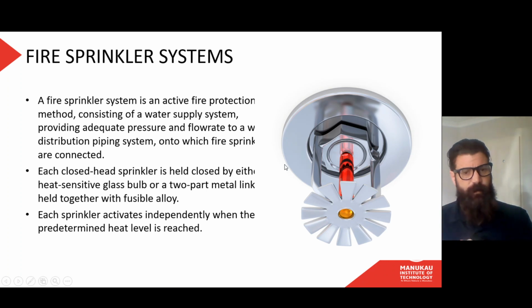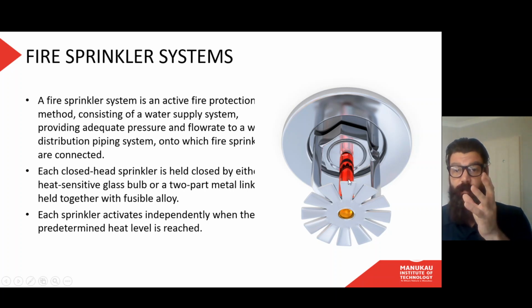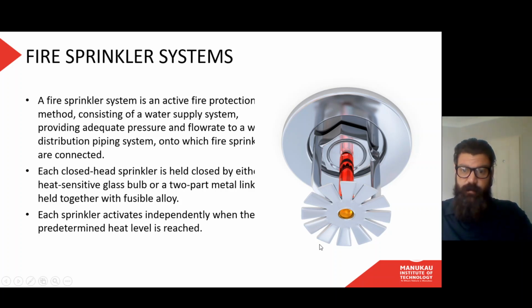Fire sprinkler system. As we talked about, we've got a really good picture there of a sprinkler, and you can see the little bulb with the liquid in it. That bulb is holding the valve closed at the top. Once the liquid reaches a certain temperature, it expands, smashes the glass, and water comes spraying out. The little star-shaped thing at the bottom is not where the water comes out. The water comes out at the top. What the star-shaped thing does is create a spray. The water comes straight down, hits that little star-shaped bit at the bottom, and that spreads it out. I don't think there's anything on that slide that I haven't already mentioned.